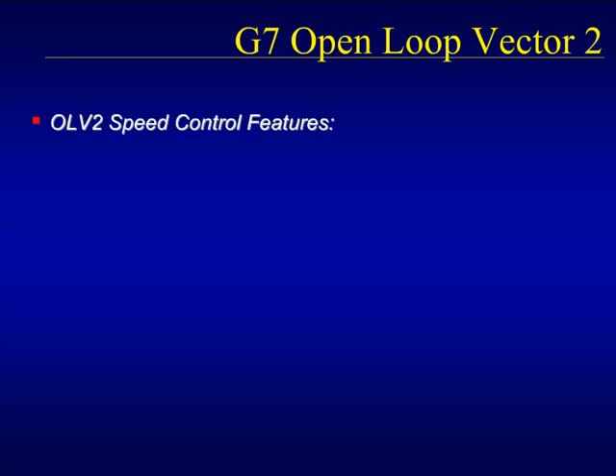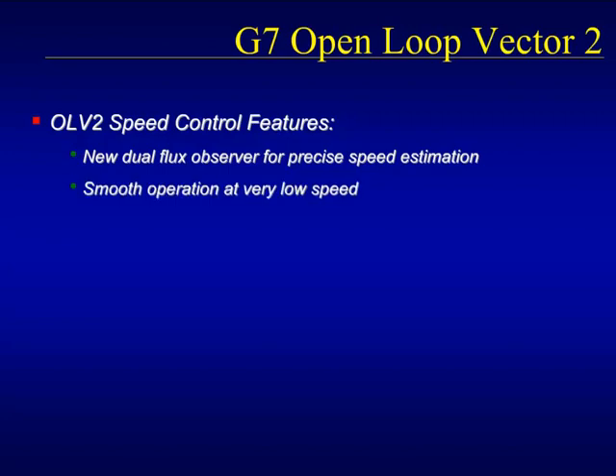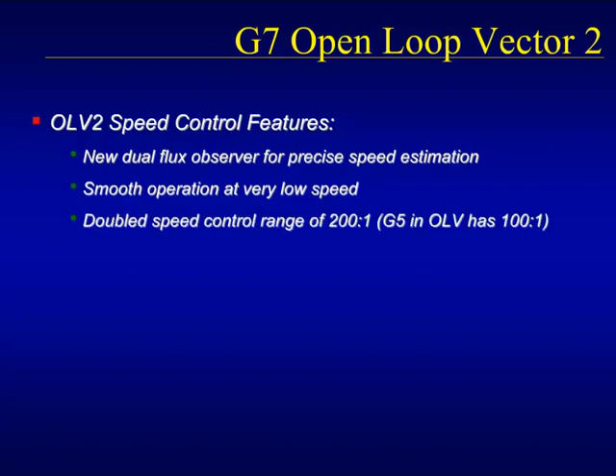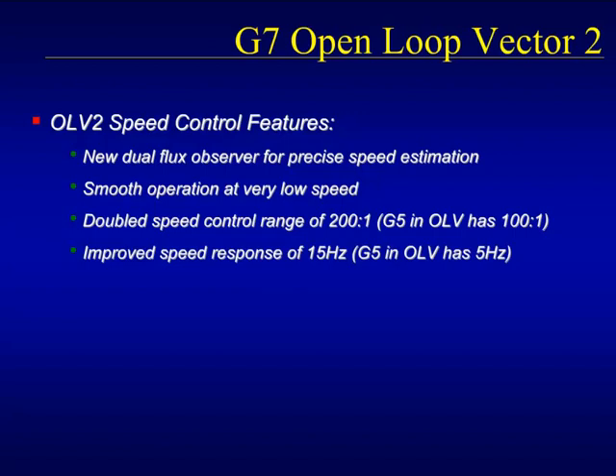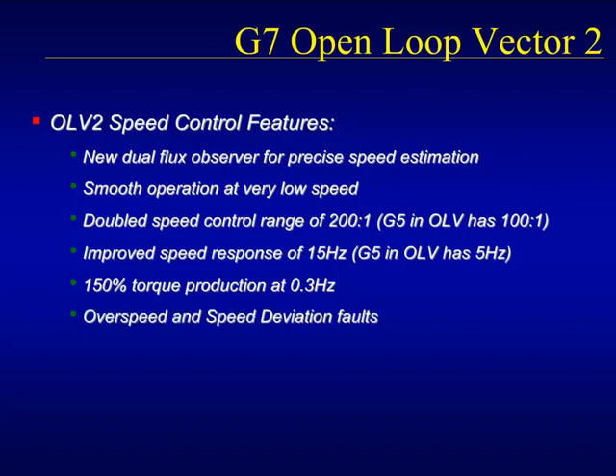The G7 offers improved open-loop vector performance due to a sophisticated dual flux observer used by its open-loop vector 2 mode. The new flux observer offers better speed regulation without feedback than was possible before. Precise speed estimation leads to some significant performance achievements such as smooth motor operation without cogging at speeds even below 1 Hz, an effective speed control range that is double that of the open-loop vector mode of the G5, speed response that is 3 times as fast as the open-loop vector mode of the G5, and the ability to produce 150% of the motor's rated torque at speeds as low as 0.3 of a Hz. Also, the open-loop vector 2 mode can recognize motor speed deviations even without the use of real-time feedback. Like the closed-loop and open-loop 1 vector control modes, 4-quadrant torque limiting is also possible with the open-loop vector 2 mode.